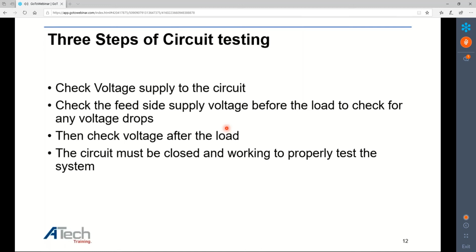A lot of you are out there using ohm meters. Ohm meters work great as long as there is a spec for it, then we test with it. An ohm meter also gives us continuity, but the problem is I can have a wire with just one strand left and still have continuity. So again, it's always best to check with the circuit working.